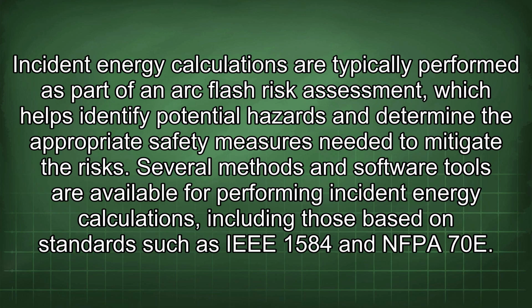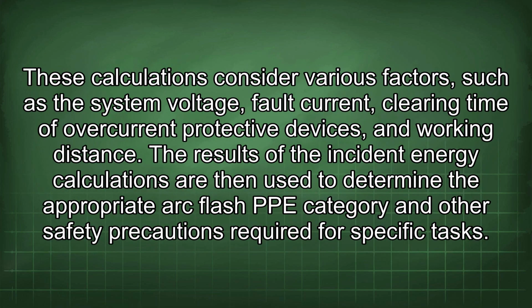Several methods and software tools are available for performing incident energy calculations, including those based on standards such as IEEE 1584 and NFPA 70E. These calculations consider various factors, such as the system voltage, fault current, clearing time of overcurrent protective devices, and working distance. The results of the incident energy calculations are then used to determine the appropriate arc flash PPE category and other safety precautions required for specific tasks.